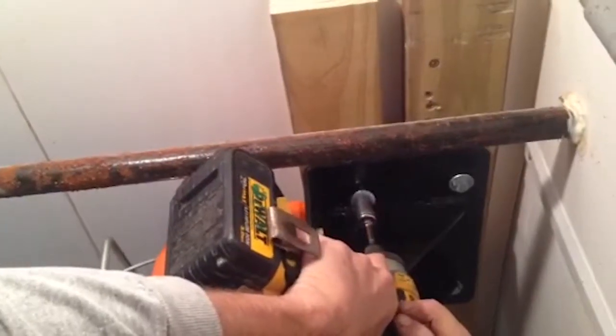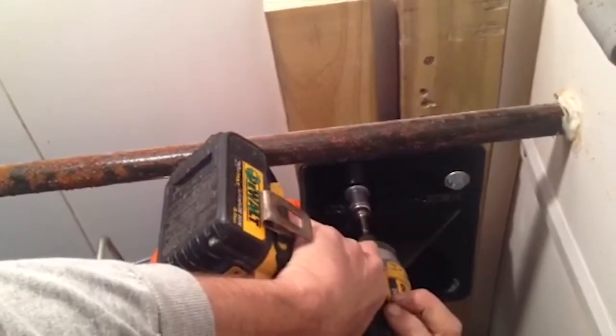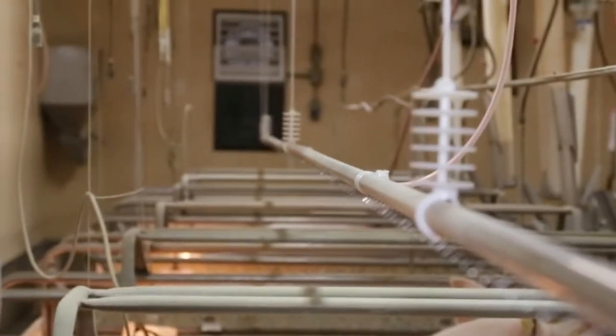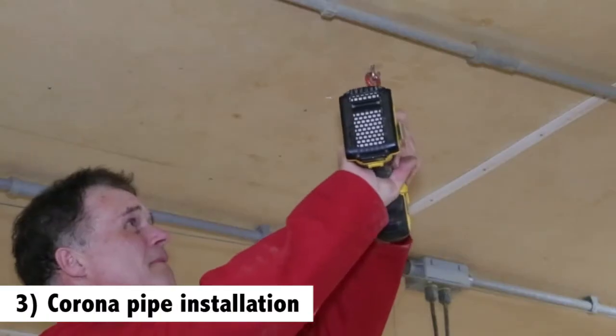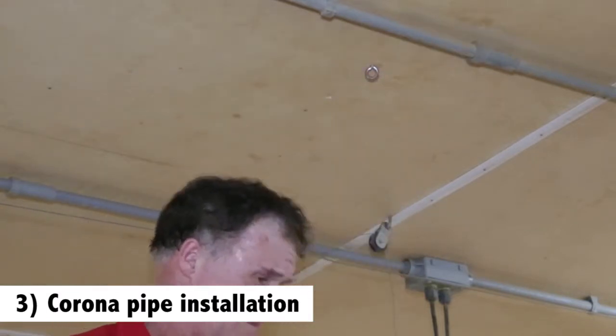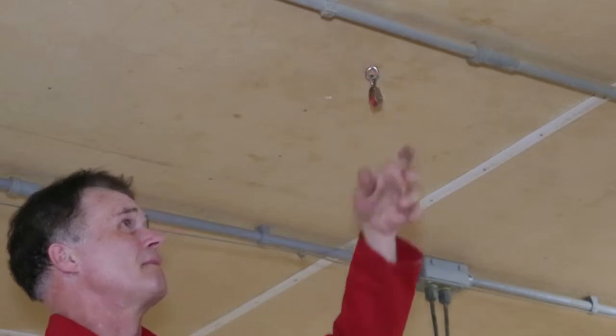Now, mount the winch to the installed lumber using the provided hardware. The corona pipe must be supported every 12 feet with a pipe insulator. A 1 1/8 inch eye lag hook support and a 7 1/8 inch pulley must be installed every 12 feet at each support location.